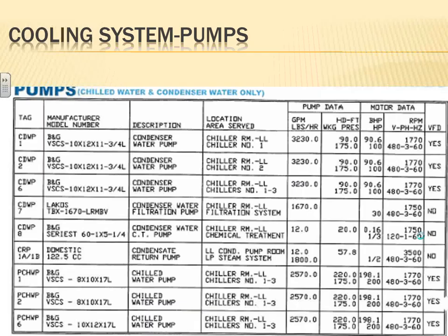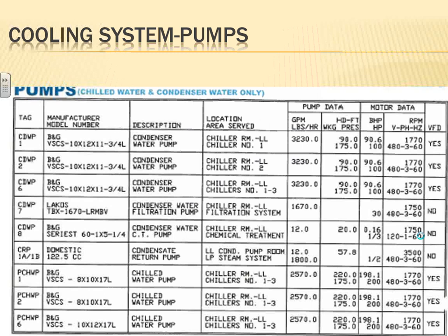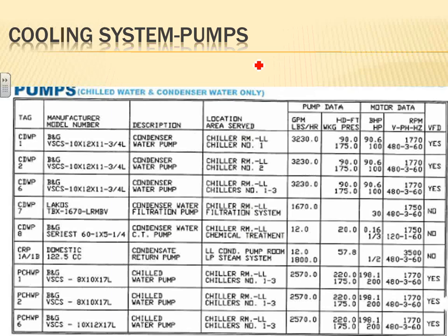This builds the whole system together and gets you the electrical components that you need to worry about and pick in terms of sizing. So for this, it will be your Article 430. You apply Article 430; Article 440 and all these calculations apply only to the compressor equipment. And of course, the one above it here is also Article 430, not Article 440. They're all pumps and fans.